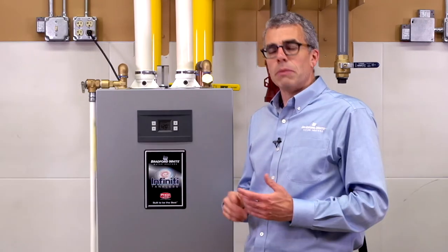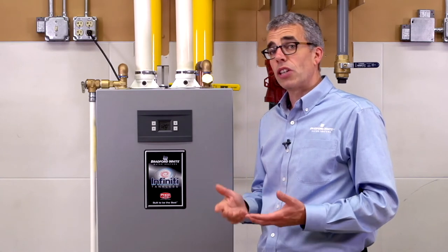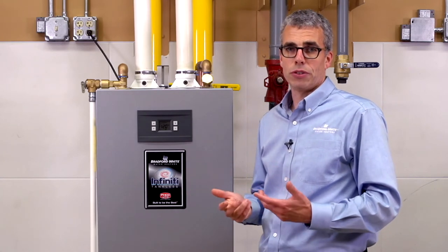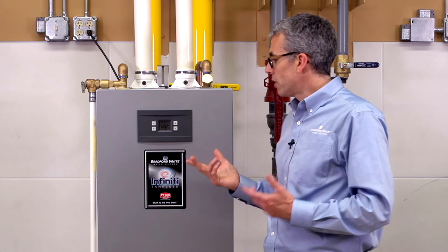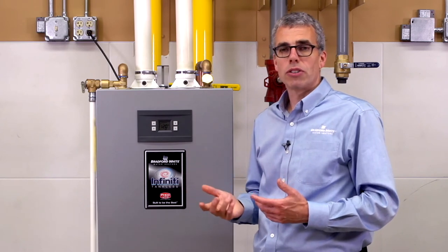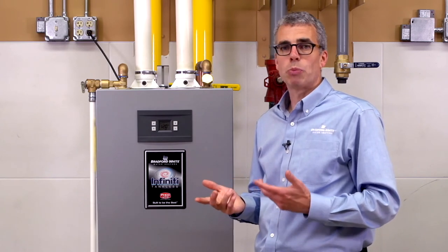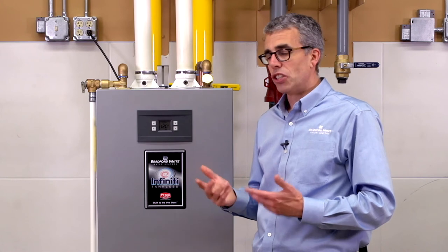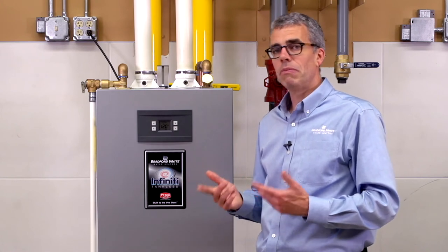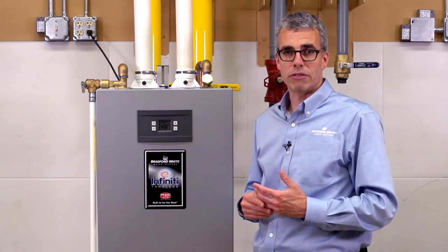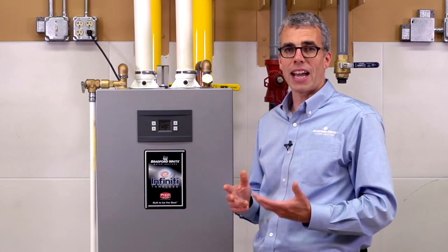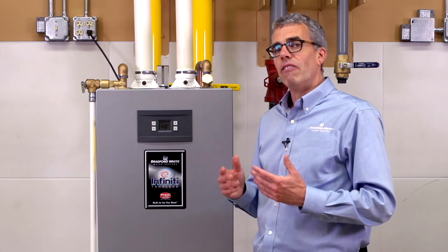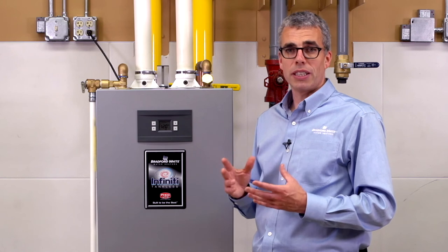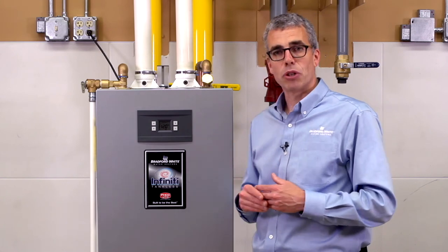In some situations, you may run into water heaters that don't turn on when certain fixtures are turned on. Now, this is a flow-activated water heater, and it requires only 0.45 gallons per minute to activate. It's not a lot of flow, but some faucet aerators are highly restrictive, and they're closer to the half-gallon per minute side. Very little needs to be restricted in order to prevent that product from turning on.